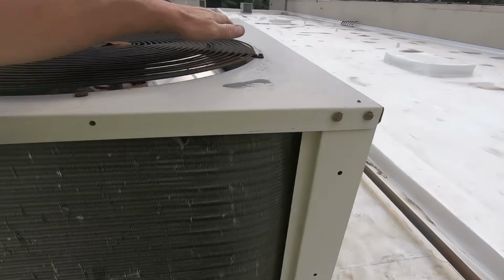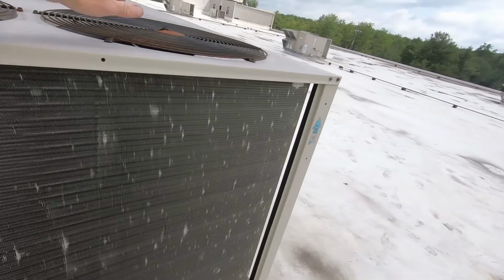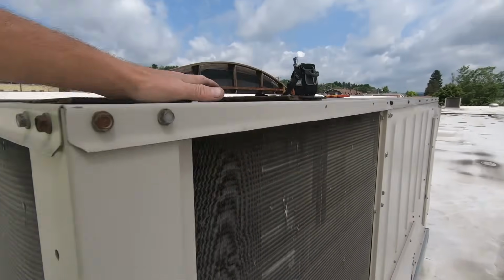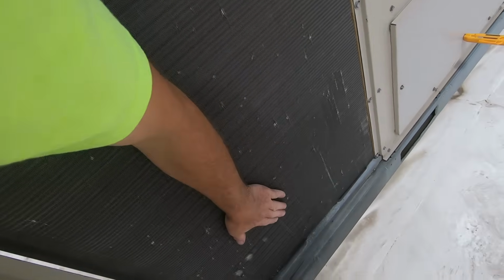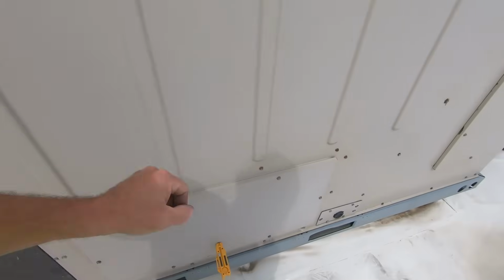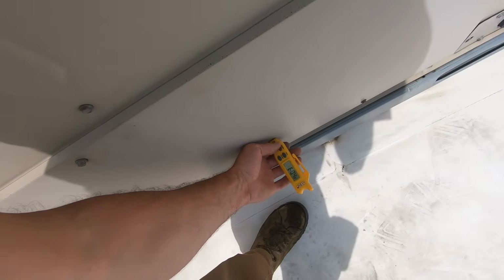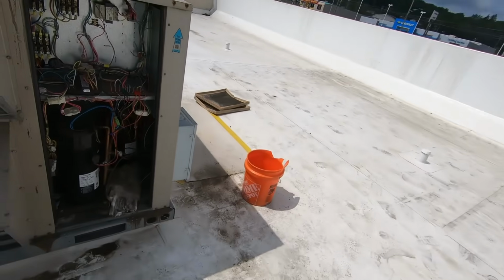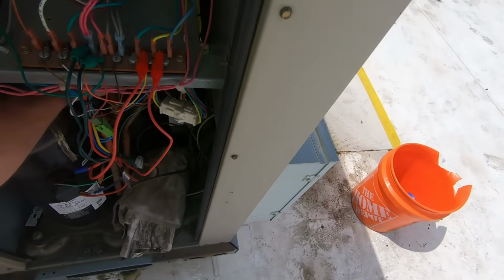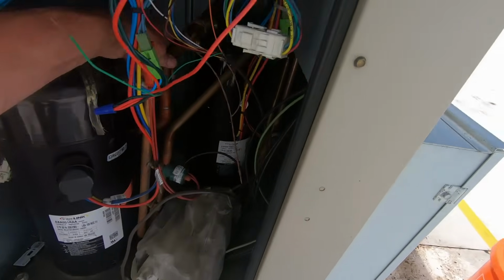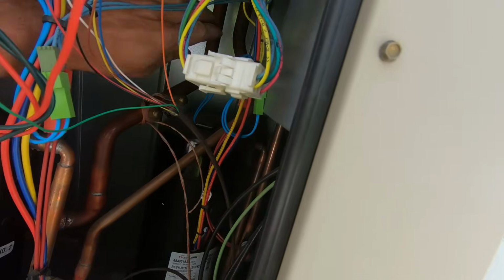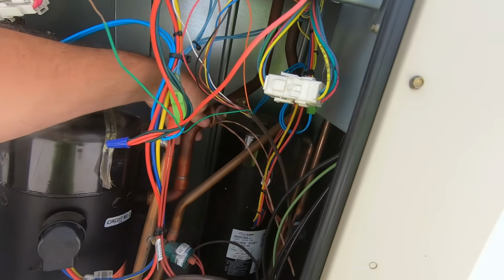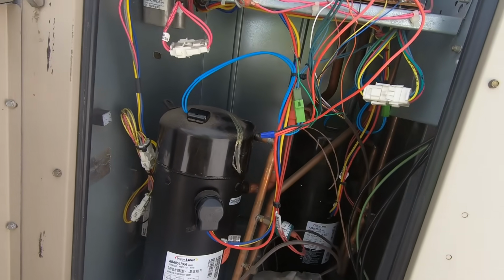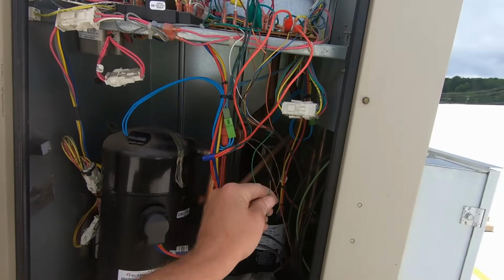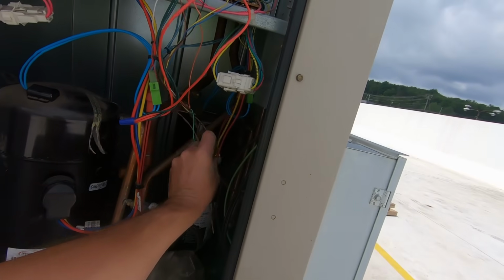They're dumping heat. Possibility on a very hot day, but first thing we need to do is clean everything. You can see it's all packed up in there, and they are hot. So I'm not surprised. 60 degrees and dropping. So I'm going to check them mechanically quickly, make sure there's refrigerant, make sure they're kicking on. That suction line's nice and cold. Oh yeah, let's see how this guy feels. Very nice and cold. So you can criticize, but the do not exceeds on these are very small, and I just want to run through and see what works and what doesn't and make my recommendation.